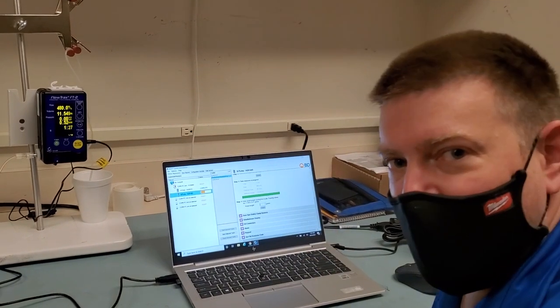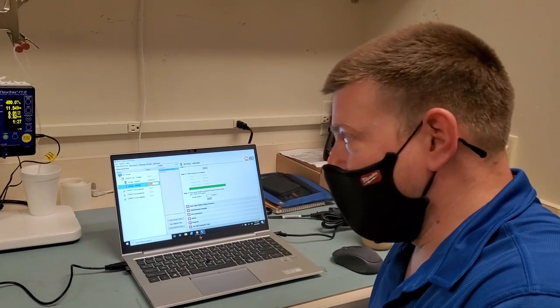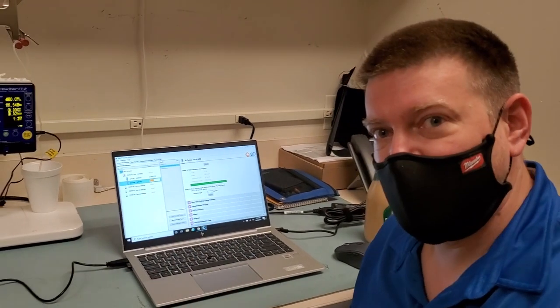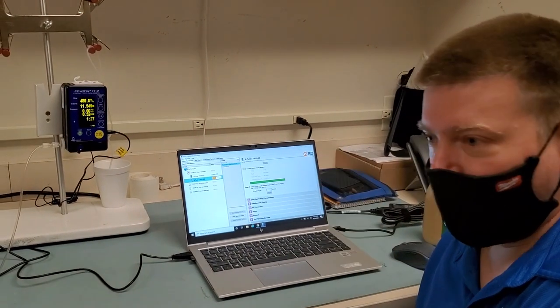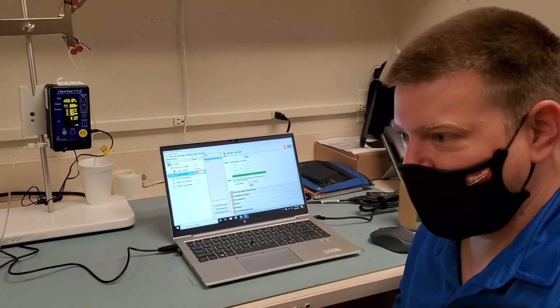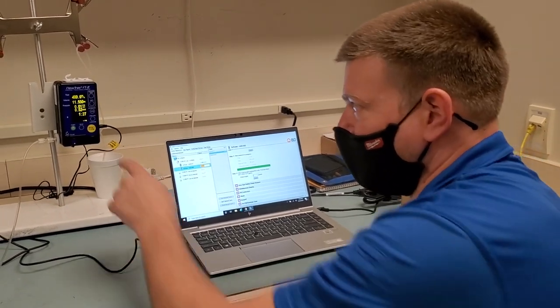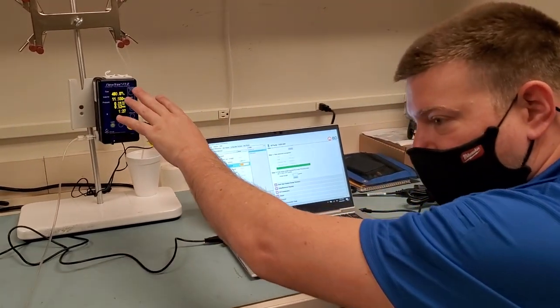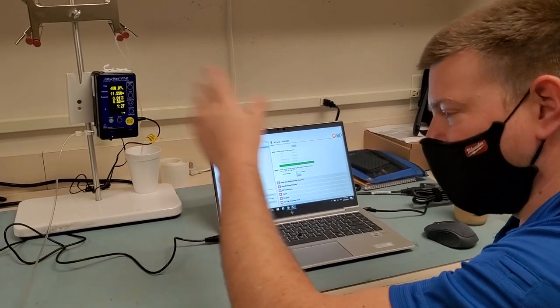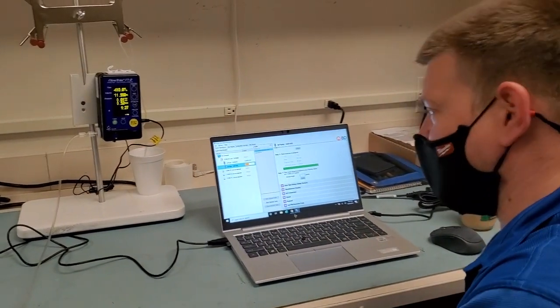Simple as that. All right, guys. Thanks for watching. I hope you found this a little bit informative. The FlowTrax really is a versatile system, and you can use it well with this Alaris system. It's very exact. And in this case, it shows you problems that are going on with your modules quite literally. We could export these results if we wanted to and make it an attachment for a work order. We're not set up here for that, but that's okay.